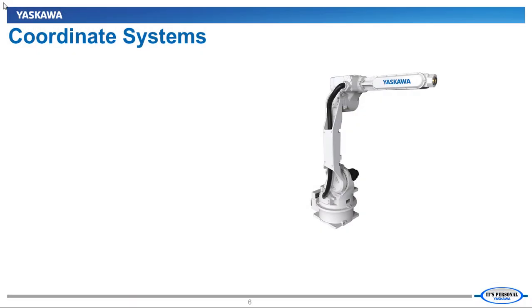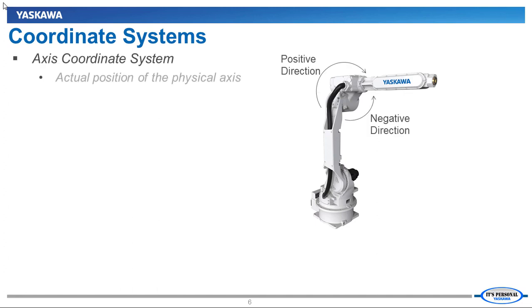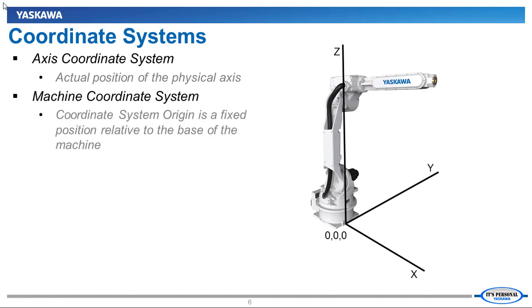PLCopen Part 4 defines four coordinate systems that can be used to control the machine. The first one is the axis coordinate system, which is used when working with a single axis of the machine — there is normally only a positive or a negative direction for this system. The second one is the machine coordinate system, which revolves around where the base of the machine is located. In the diagram here, the origin is located at the base of this robot arm, and any position given relates to the base position.